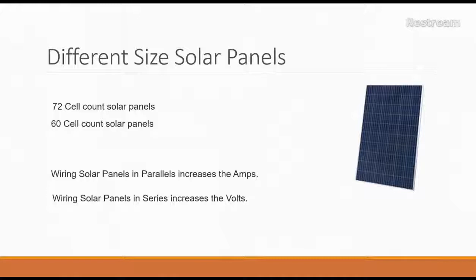Series means more volts. In order to turn on an inverter, it may need a certain amount of volts to turn it on. So you may try to wire it to 12 volts and wonder why it doesn't come on, then you read the manual and say, hey, I need at least 18 volts. That's when you would wire your panels in series to get more volts, so it would turn on the inverter and make the charge controller work. So those are things you have to be aware of when you are doing that.